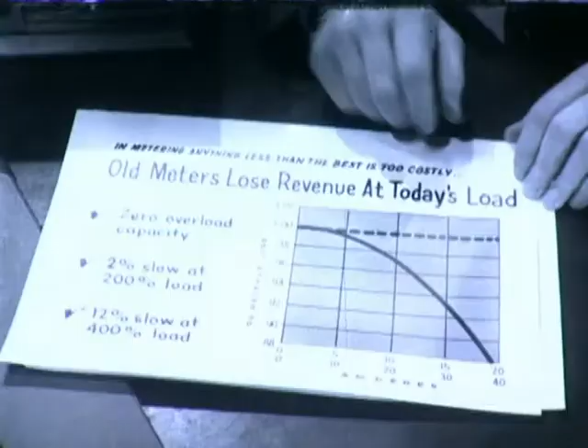A 5-amp watt-hour meter built before 1927 can be as much as 2% slow with just a single 1,000-watt appliance on the circuit. If your customer loads the circuit up to 4 times the meter rating, he gets an automatic 11% discount from the meter, even though the meter shows perfect calibration at both the full load and light load checkpoints.